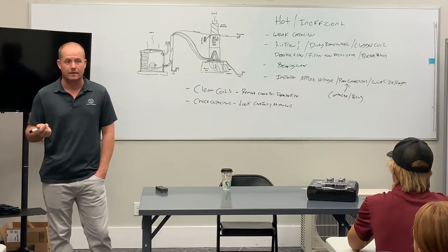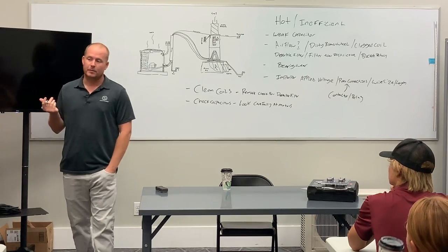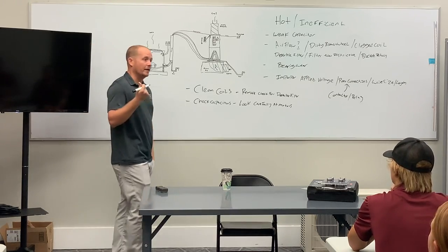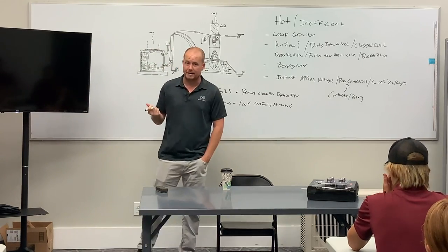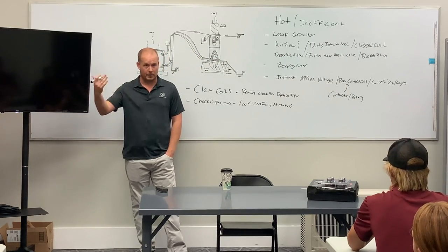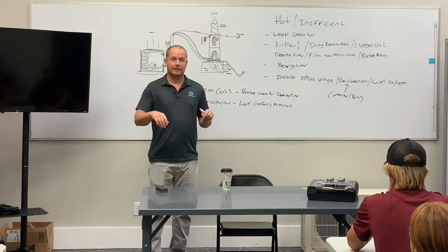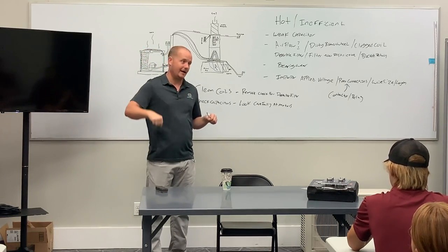Now, that doesn't mean that you tell the customer, oh my gosh, you need to change this motor. But it is something, depending on the attributes of the customer, you can go ahead and mention it. There's nothing wrong with that. That is a sign of an emerging problem. And you check for shaft play. Shaft play is this way, not in and out, right?